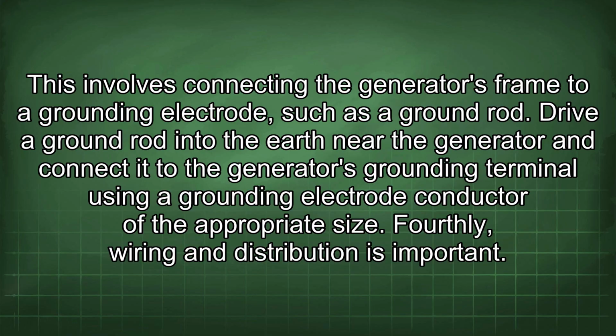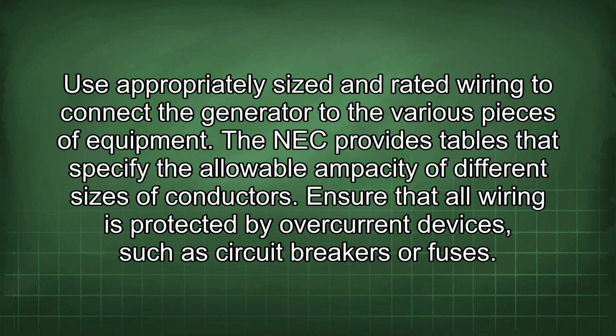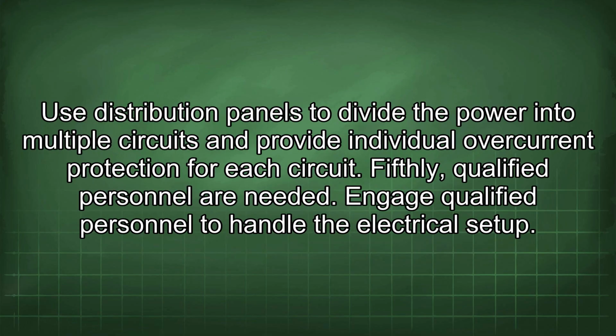Fourthly, wiring and distribution is important. Use appropriately sized and rated wiring to connect the generator to the various pieces of equipment. The NEC provides tables that specify the allowable ampacity of different sizes of conductors. Ensure that all wiring is protected by overcurrent devices, such as circuit breakers or fuses. Use distribution panels to divide the power into multiple circuits and provide individual overcurrent protection for each circuit.